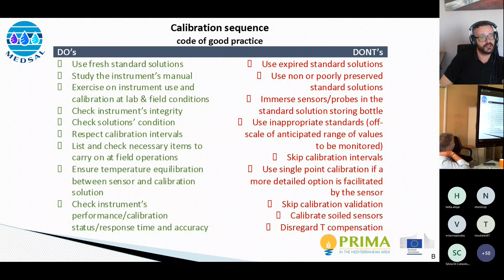Of course, the instrument has to be checked for its integrity, and also the solutions that you use for the calibration. Please respect the calibration intervals. Don't, let's say, use only one if you have to use 2 or 3 calibration intervals, especially for pH. You have to make a checklist and have it with you when you go to the field. Sometimes it is pretty far from our office. There are things that we cannot find easily. Moreover, please ensure the temperature equilibration between the sensors and the calibration solution. And of course, we have to check the instrument performance, calibration status, and response time and accuracy.